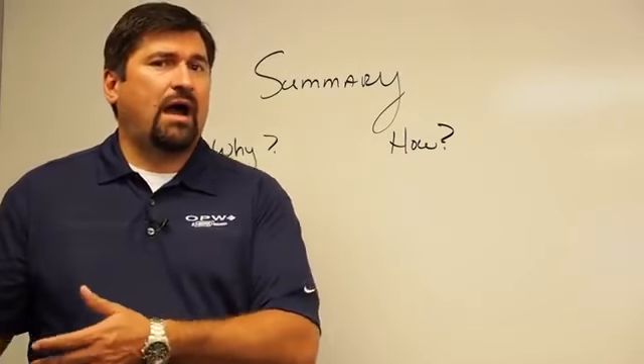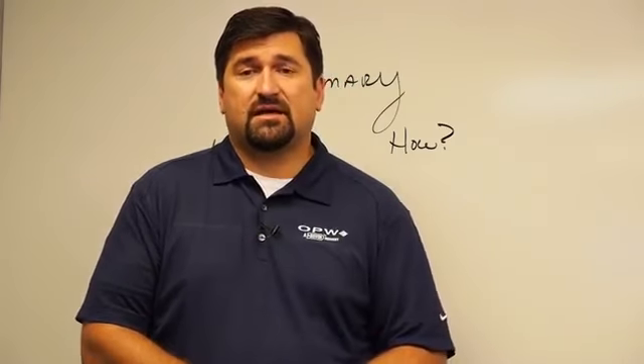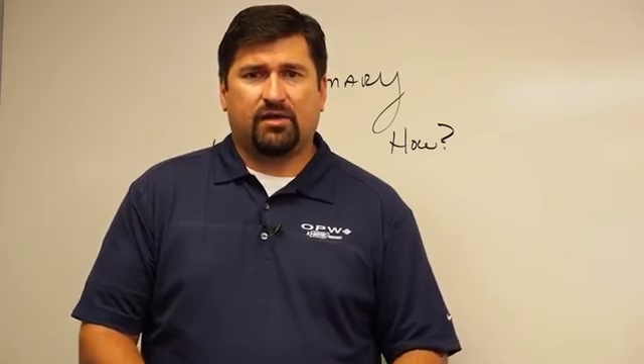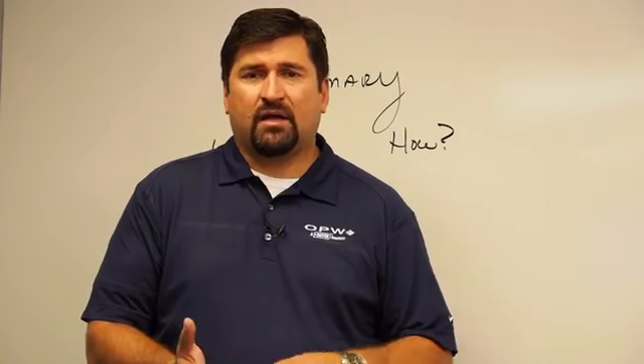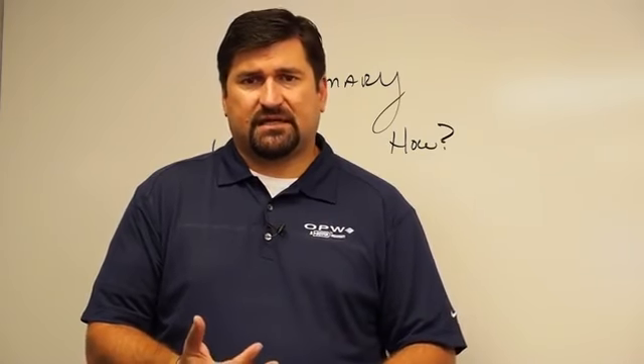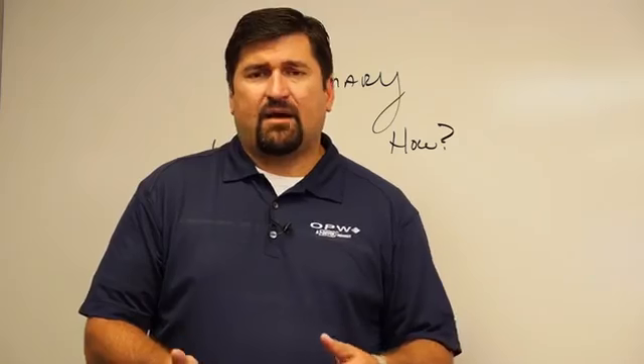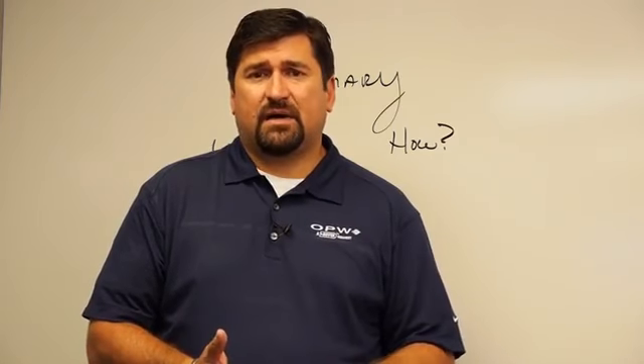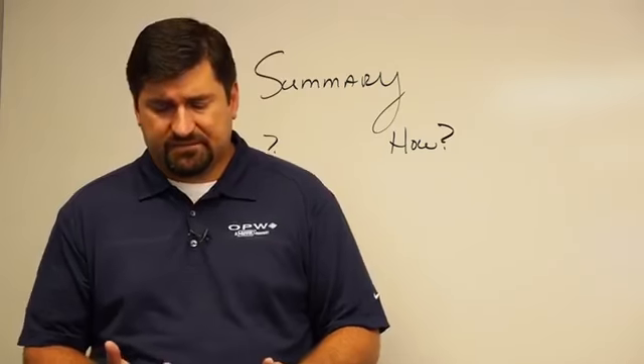The piece that you need to look at doing is going out and selling them on the why. Why do you need the ATG? That's going to be the part that you need to go back and look at trying to sell them on. Basically, why do you need it? Lower cost of ownership of your station, because you're not paying somebody to go out, go to the tank site, stick a stick in the tank, try to figure out where you're at with the gauge. And with the implementation of 40 CFR and the pressurization of the tanks, you're going to be inaccurate with the stick because the tank may be under pressure or vacuum, and that will distort your actual tank inventory readings by 3 to 4 inches, either plus or minus.